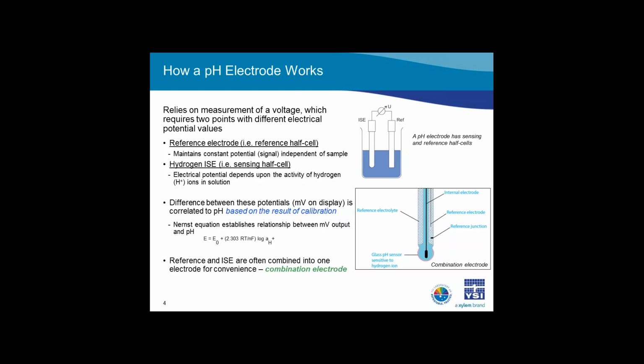The reference electrode and the hydrogen ISE can be separate electrodes, or they can be combined into a single electrode for convenience. The combination style electrode is used in about 90% of all pH applications, and all YSI electrodes are of this combination type.